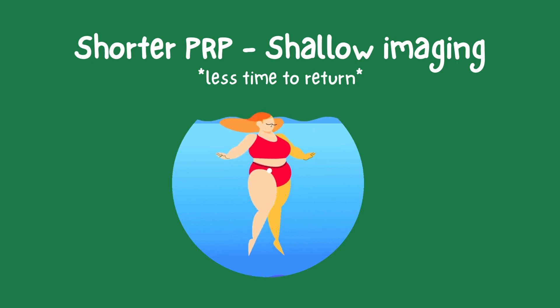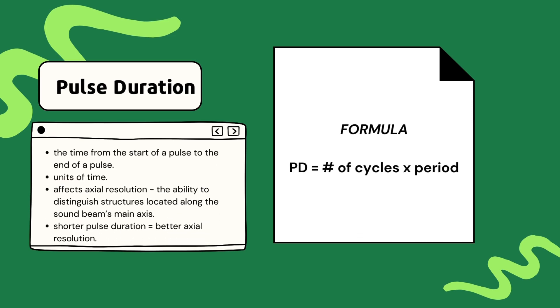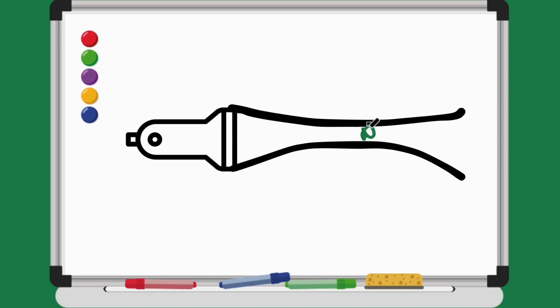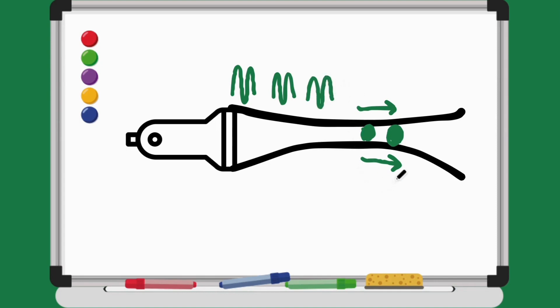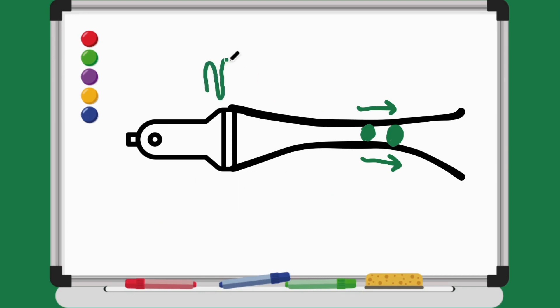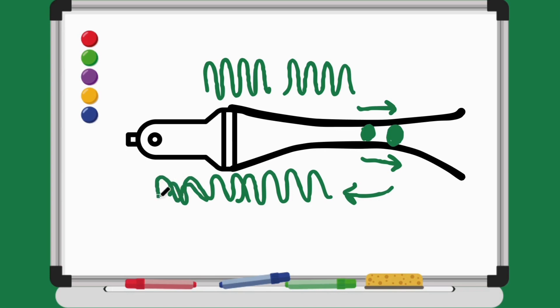Now we're going to discuss pulse duration. Pulse duration simply refers to the time it takes for one ultrasound pulse to occur — the time from the start of a pulse to the end of it. Pulse duration plays a critical role in determining the clarity and precision of ultrasound images, particularly in the axial direction. Axial resolution is the ability to distinguish between two structures that lie along the direction of the ultrasound beam, and it is greatly influenced by pulse duration. Shorter pulses are better for axial resolution — the system can precisely locate returning echoes, making images sharper and more defined. Longer pulses may degrade axial resolution because returning echoes can overlap, blurring structures along the direction of the beam and making it difficult to distinguish true details.